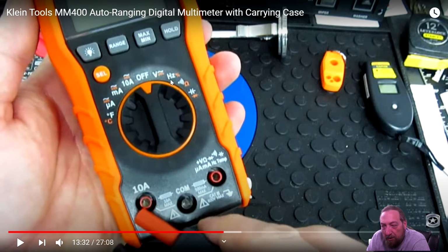The hertz is when you're testing a refrigerator with a variable speed compressor, and the inverter board's on the compressor, but it has a separate main board like Electrolux. You need to check voltage from one board to the other to see if they're communicating. And one of the tests that you make is frequency. When the compressor's running at top speed, I think it's like 250 hertz or something like that. So if you put this on hertz, you can measure the frequency coming from one board to the other, knowing that the main board is telling the inverter board how fast to run. And also if it's getting a communication. But the funny thing is that same two wires has both AC and DC voltage. And sometimes the prongs are so small, you need to use those real fine points that I use.